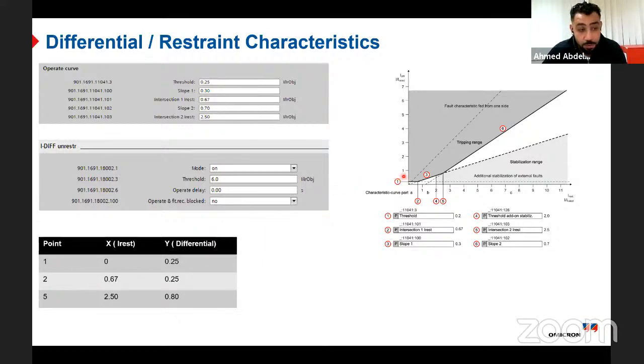Point number 1, which is here, you can see if you have a direction or a relation between X and Y. So point number 1, what is the X coordinate for it? It's 0 because it starts from 0, and Y is the minimum operating current, so it will be 0 and 0.25. Point number 2 is very clear. You have the X coordinate because it is here in the manual, the X coordinate for intersection 1, which is 0.67, and you need the Y coordinate. You can see point number 2 is on the first segment and on the second segment. So the Y coordinate of point 2 should equal the Y coordinate of point number 1. So it will be 0.25.